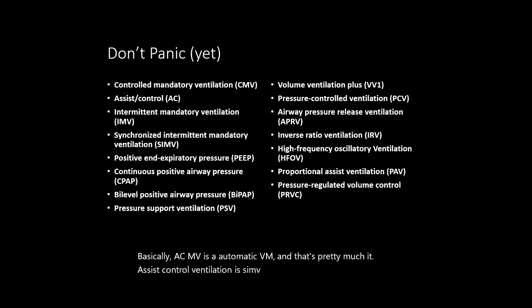Something that you don't see very often is CMV, or controlled mandatory ventilation. The old auto vent 1000s were CMVs. Basically, a CMV is an automatic BVM. And that's pretty much it. Assist control ventilation is CMV with some assist for extra spontaneous breaths. Intermittent mandatory ventilation is pretty much what it sounds like. And SIMV, synchronized intermittent mandatory ventilation, is basically where we'll try to time some of the intermittent breaths with the breaths that the patient takes.